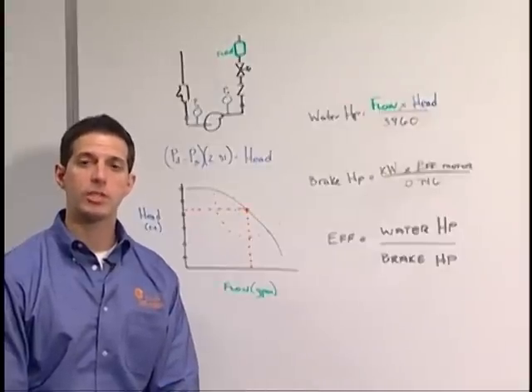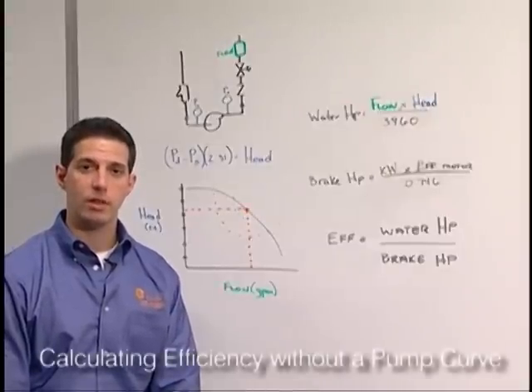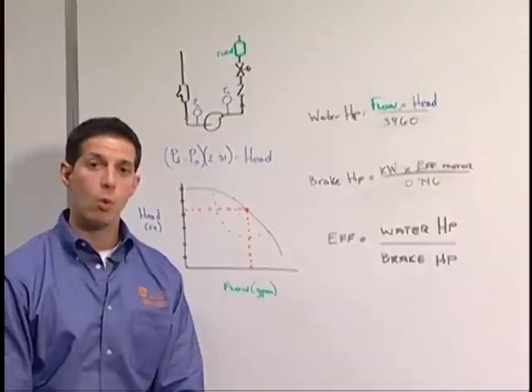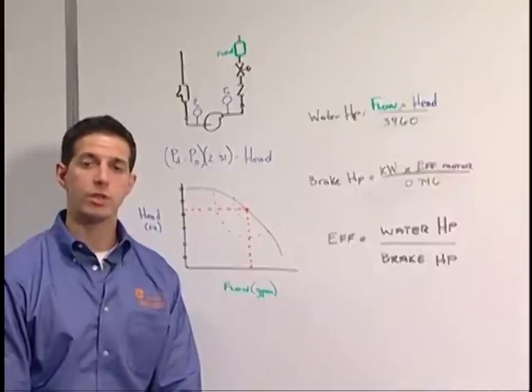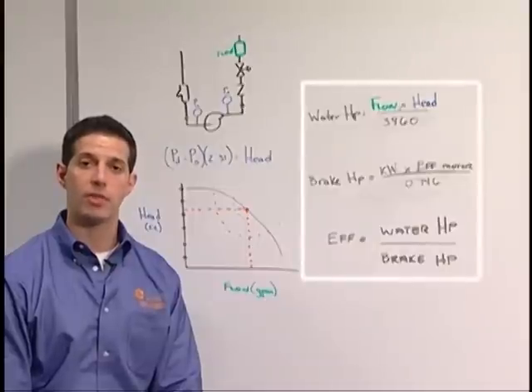If you don't have a pump curve, you can still calculate the pump's efficiency. This is done by correlating water horsepower to brake horsepower. Water horsepower is calculated using the flow and the head divided by 3960.